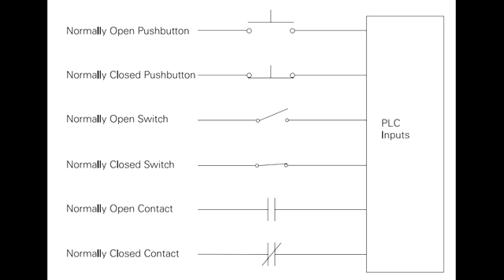Discrete input. A discrete input, also referred to as a digital input, is an input that is either in an on or off condition. Pushbuttons, toggle switches, limit switches, proximity switches, and contact closures are examples of discrete sensors which are connected to the PLC's discrete or digital inputs. In the on condition a discrete input may be referred to as a logic 1 or a logic high. In the off condition a discrete input may be referred to as a logic 0 or a logic low.